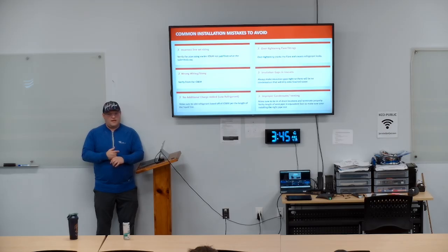Okay. And what that means, that doesn't mean, oh, I got there in 20 foot, but I have 3 90s. That means every 90 is 5 foot. So if you have 3 90s, that's 15 foot. You can only run a pipe 5 feet, then you got to upsize it to 3-inch. So make sure you're thinking about that stuff. If you don't understand it, ask me.